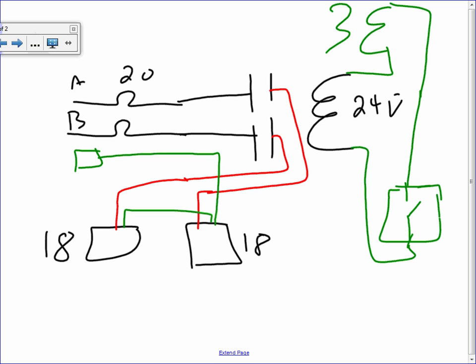There you go, so I have my low voltage switches - remember, this is 24 volt, coming from a 120 volt feeder. You have 2-pole or sometimes 3-pole; they use 3-pole contactors on parking lots. When you have a parking lot, you can have an occupancy sensor or a timer drive this relay to control the lights in the parking lot.